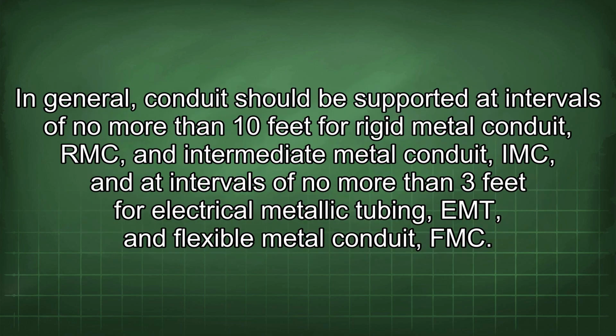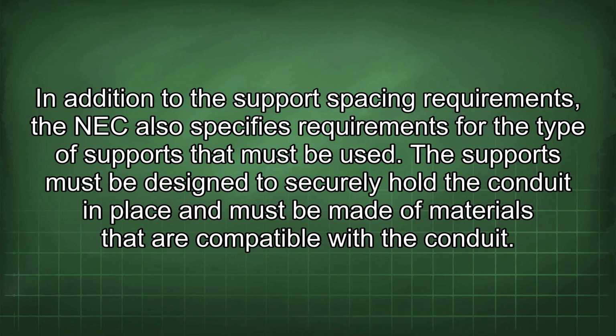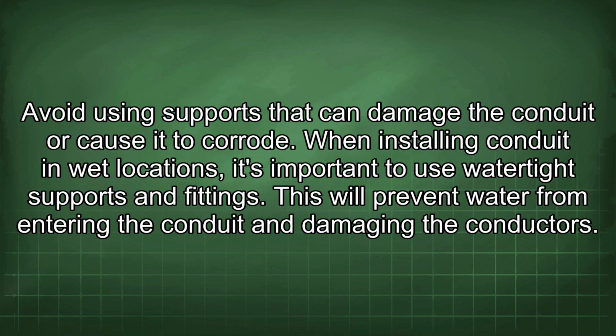In general, conduit should be supported at intervals of no more than 10 feet for rigid metal conduit, RMC, and intermediate metal conduit, IMC, and at intervals of no more than 3 feet for electrical metallic tubing, EMT, and flexible metal conduit, FMC. In addition to the support spacing requirements, the NEC also specifies requirements for the type of supports that must be used. The supports must be designed to securely hold the conduit in place and must be made of materials that are compatible with the conduit. Avoid using supports that can damage the conduit or cause it to corrode.